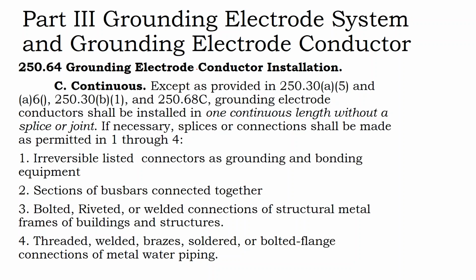But on that last stop, where your equipment ground conductor is all interconnected, and that can be at any point on that equipment ground conductor system, that last leg of the journey between the equipment ground conductor system and your grounding electrode conductor needs to be continuous. And that's almost kind of weird, because imagine your building to be a big square, and this can be at any point off that square before you get to your ground rod. But it's just saying there are more robust requirements for that last leg of the journey to make sure that it never fails, and that if you have a ground fault situation, it's properly sized so that it doesn't heat up, so that it can clear the ground fault without burning your building down.